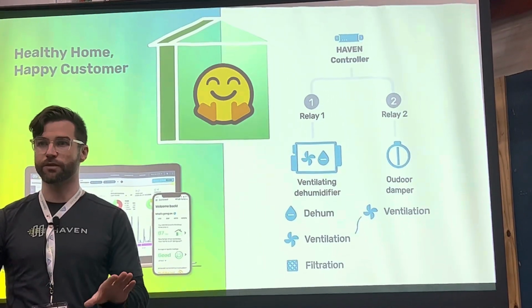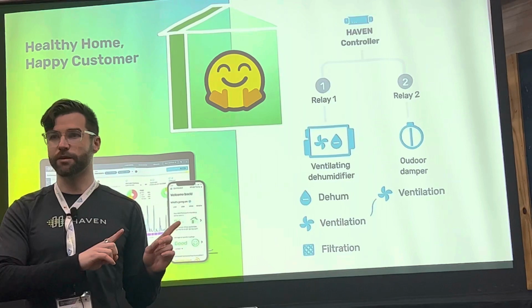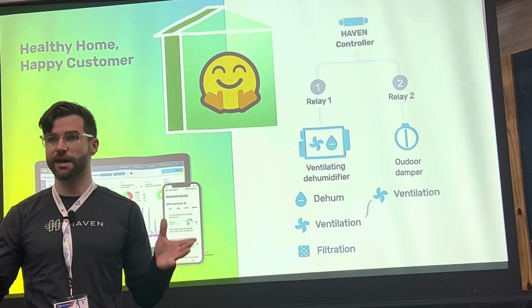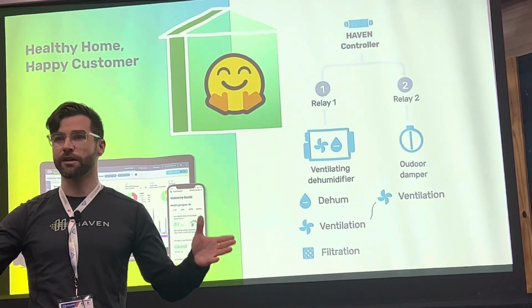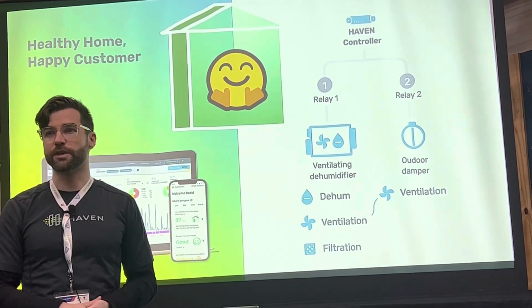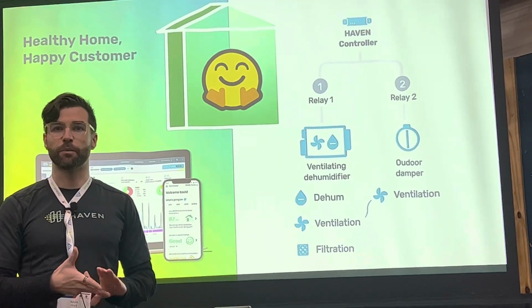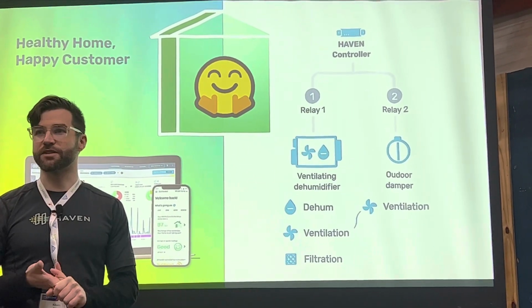Systems to dedicated pieces of equipment that are expensive and hard to install, this eliminates the need for a complicated piece of ventilation equipment. You can simply attach, whether it's a 6, 8, or 10-inch duct from your outdoor air through a motorized damper and dump it into your dehumidifier.